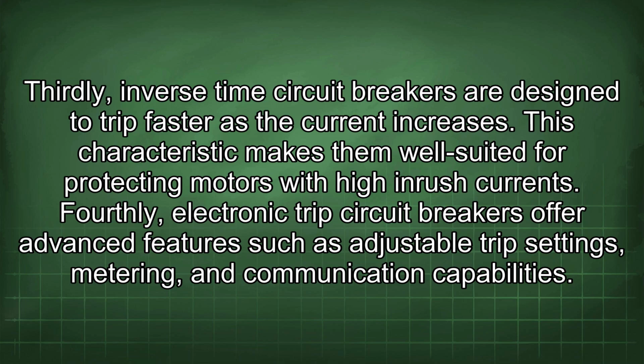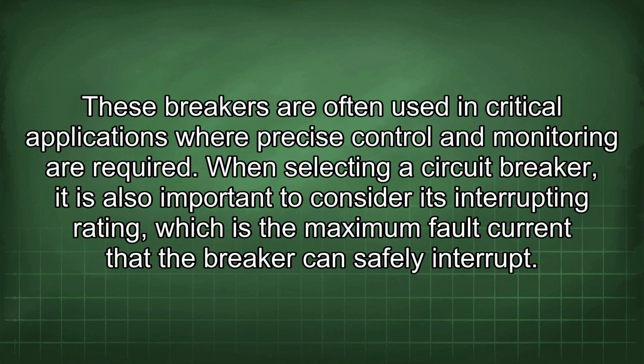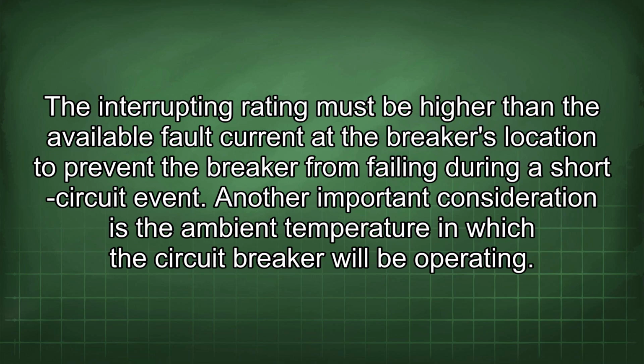Fourthly, electronic trip circuit breakers offer advanced features such as adjustable trip settings, metering, and communication capabilities. These breakers are often used in critical applications where precise control and monitoring are required. When selecting a circuit breaker, it is also important to consider its interrupting rating, which is the maximum fault current that the breaker can safely interrupt. The interrupting rating must be higher than the available fault current at the breaker's location to prevent the breaker from failing during a short circuit event.